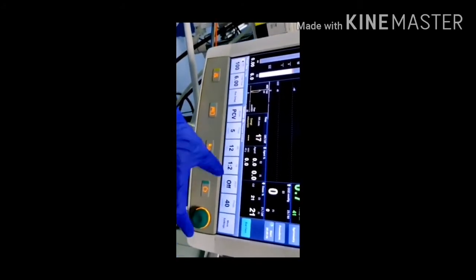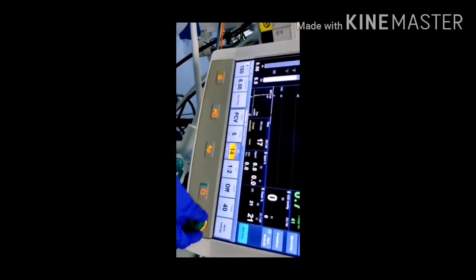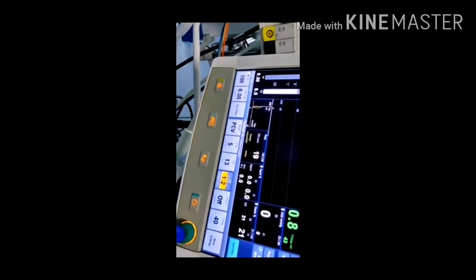Okay. Now since the new mode is selected, you have to set the controls to confirm the mode. Here the respiratory rate is asked, so you can set the respiratory rate. You can touch on the RR, select the RR and confirm. For the IE ratio, you just have to select that parameter, touch the knob and then change the values. So here we have an unable to drive bellows message. This is a case.